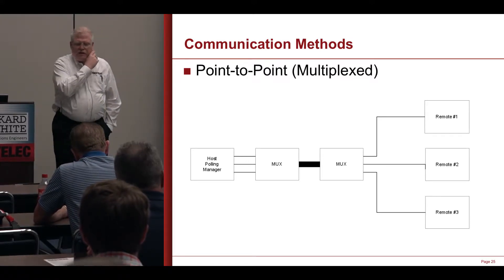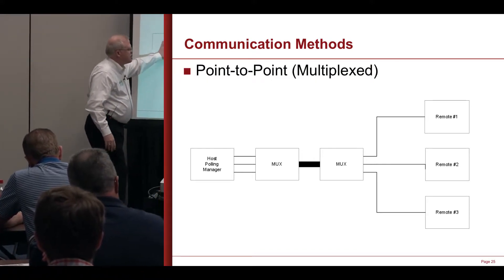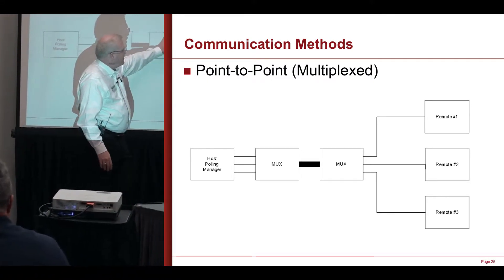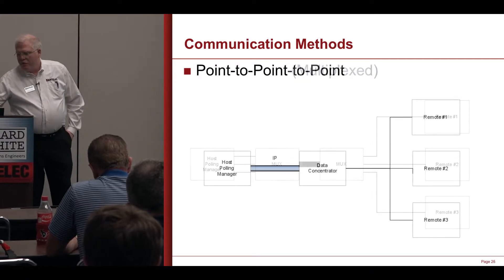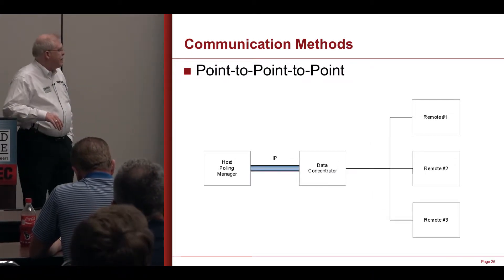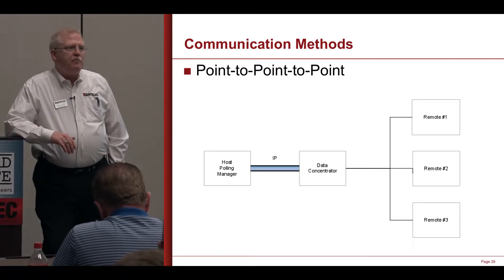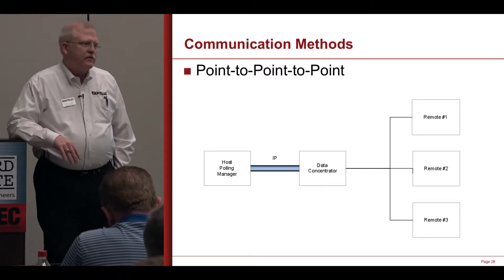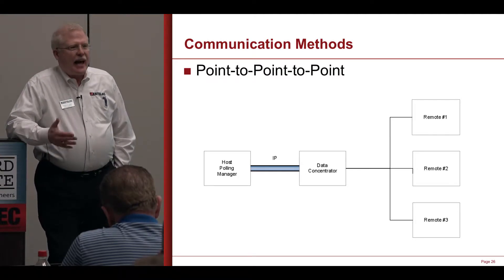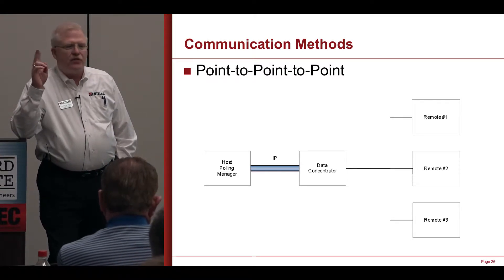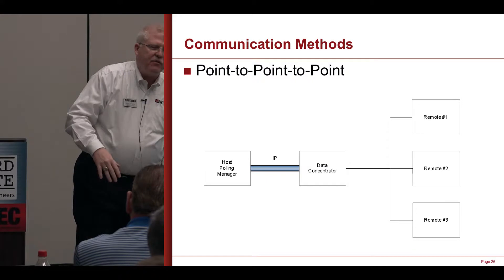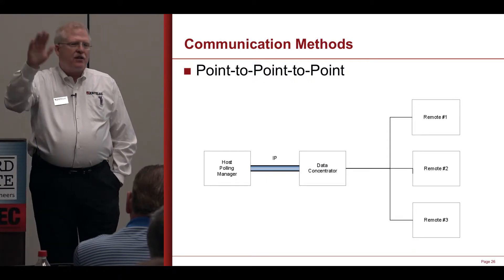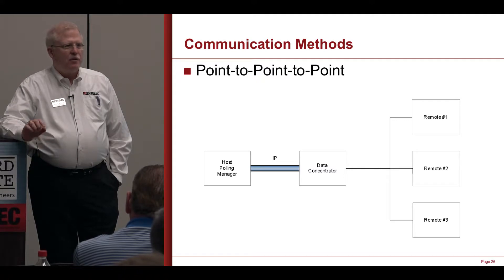The point-to-point-to-point analogy would be: here's a telephone switch, and then going through a microwave backbone, and then splitting it out. We do things like this in SCADA systems. Most places, we're either going IP all the way out to the remote, or we're going IP as far as we can down the wire, and at the last place we can, we convert that IP to serial. Underlying everything we do — all the remote telemetry, all the stuff in the field — is narrowband, poll-response, point-to-multipoint communications.